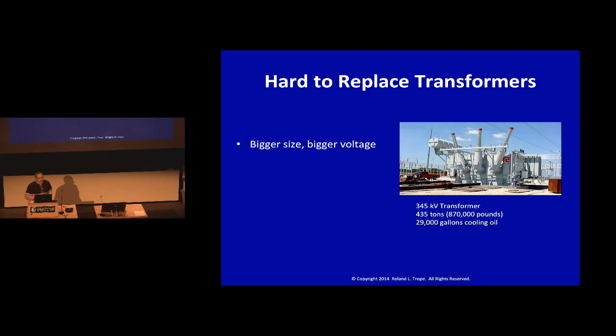Well, first, let's get a sense of the magnitude of these things. A high voltage transformer can weigh up to or more than 400 tons. It will have inside it upwards of 30,000 gallons of cooling oil. So they're large, they're heavy. The bigger they are, by the way, the more voltage they can step up or step down. But what's particularly problematic is that they tend to be unique to the substation, both in their physical dimensions and in what they're supposed to be able to do, and they are made to custom specs. So you can't go to some local dealer who has an entire showroom of the same kind or a warehouse filled with these. They are often not built except to order.